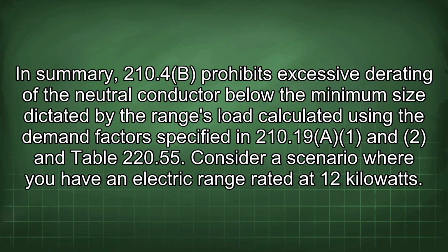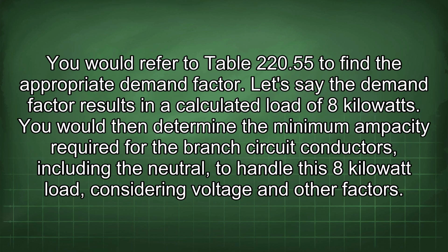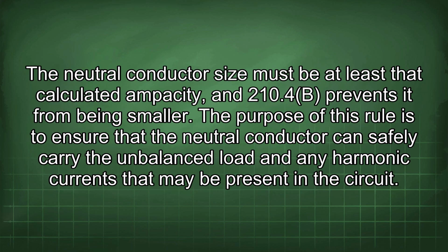Consider a scenario where you have an electric range rated at 12 kilowatts. You would refer to Table 220.55 to find the appropriate demand factor. Let's say the demand factor results in a calculated load of 8 kilowatts. You would then determine the minimum ampacity required for the branch circuit conductors, including the neutral, to handle this 8 kilowatt load, considering voltage and other factors. The neutral conductor size must be at least the calculated ampacity, and 210.4b prevents it from being smaller.